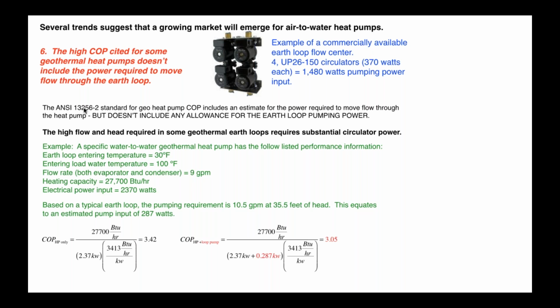And obviously you've got to pump through both. So if we, and I ran some numbers, if we put in a heat pump here with a little over 2 tons of capacity, and we do our math on the earth loop, and we include the power to operate the earth loop circulator in the COP of what I'll call the heat pump plus the earth loop circulator, because you can't operate a geo heat pump without an earth loop circulator.